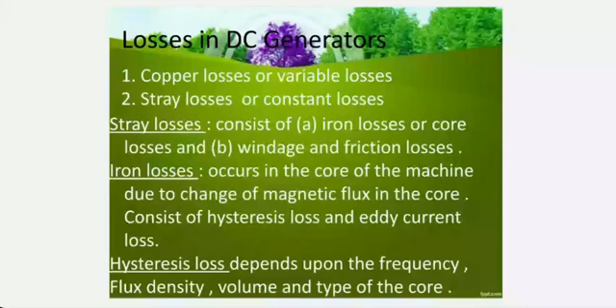There will be field winding losses. I squared R applies to field windings as well as armature windings. These losses change with load, meaning how much current you are drawing from the generator. These are the variable losses, and at high currents they predominate, producing most of the heat.